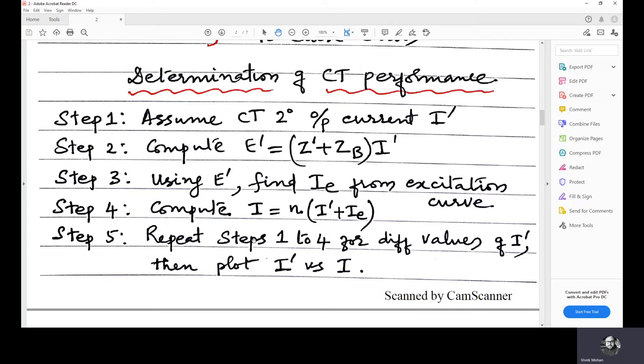Now you know i' and i. For different values of i', you will get different values of i, so you can plot i' versus i. Repeat steps one to four for different i' values and then plot i' versus i — this gives an idea of the CT's performance. The difference between i' and i should be small: i' is at a scaled-down level and i is the actual fault current, but there is a threshold for i at which the relay should operate.